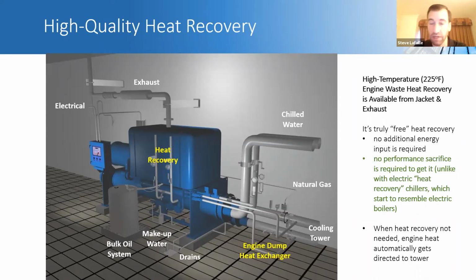We use the cooling tower to do our trimming. We can do a separate radiator if needed—sometimes when we retrofit to an existing tower we've done that. But typically you use the tower as your engine's radiator, and your heat recovery use is going to be somewhat variable throughout the day. You don't know how those loads are going to coincide perfectly, so you want a means to keep the engine at the right temperature, since your primary goal is to maintain the chilled water set point.